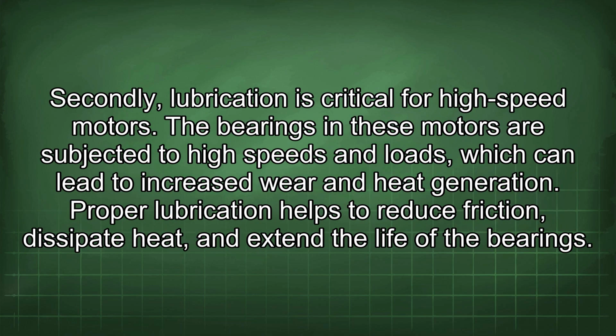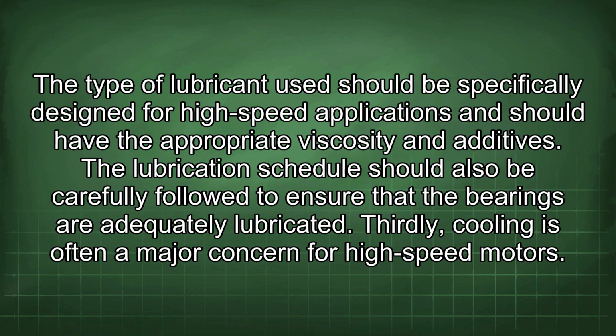Secondly, lubrication is critical for high-speed motors. The bearings in these motors are subjected to high speeds and loads, which can lead to increased wear and heat generation. Proper lubrication helps to reduce friction, dissipate heat, and extend the life of the bearings. The type of lubricant used should be specifically designed for high-speed applications and should have the appropriate viscosity and additives. The lubrication schedule should also be carefully followed to ensure that the bearings are adequately lubricated.